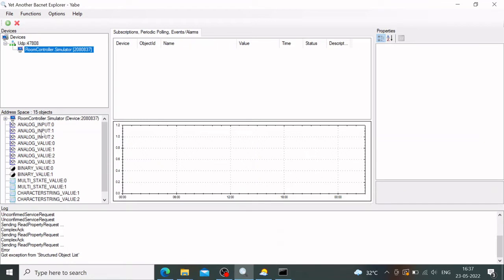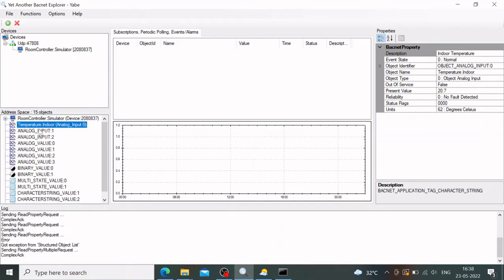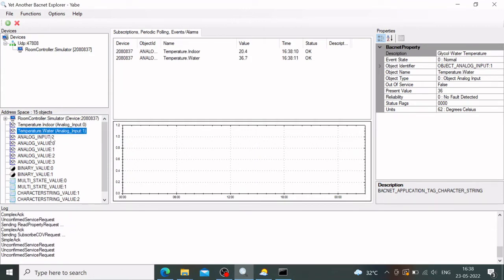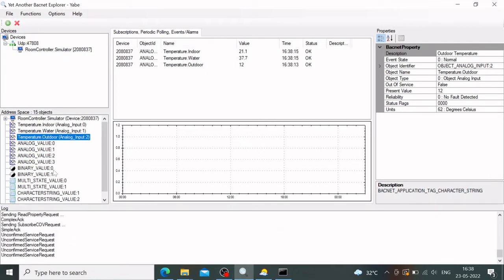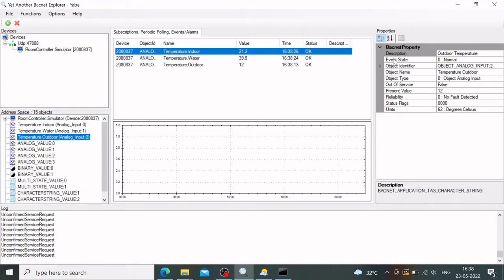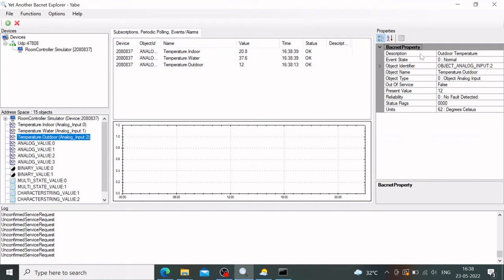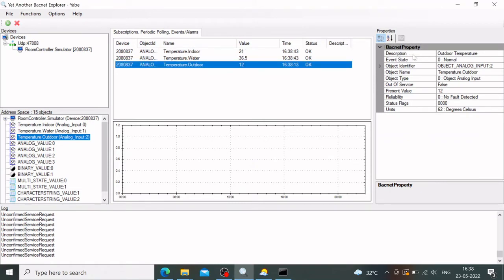You can see different inputs available: Analog Input 0, Analog Input 1, Analog Input 2. Drag and drop them to view details — Analog Input 1 is indoor temperature, Analog Input 2 is outdoor temperature. When you select an analog object, you can see all the BACnet properties: description, object type, out-of-service status, present value, reliability, and more. These are the properties we explained thoroughly in Part 1.